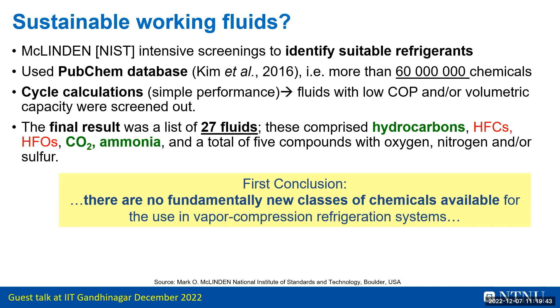Also, if we do a refurbishment or retrofit of an old system, we have a challenge if we use these new short-life fluids, which are mainly flammable, while the old system was not designed to contain a flammable fluid from the safety point of view. It's not a wise decision to just change the fluid—the properties are slightly different, so it has to be adjusted. In some cases it makes sense if the system still has some years of operation and needs a fluid. But for new systems, it doesn't make sense at all to use these fluids, because they're very soon forbidden in Europe.